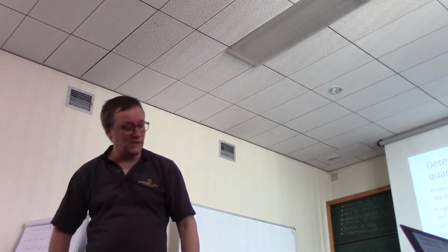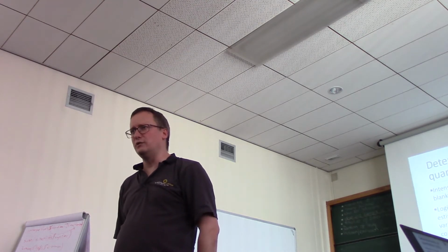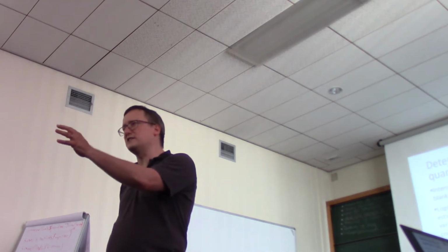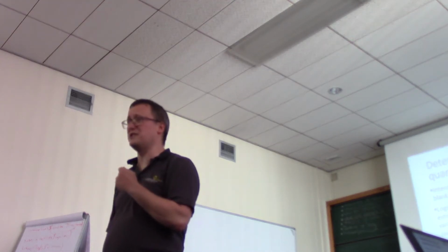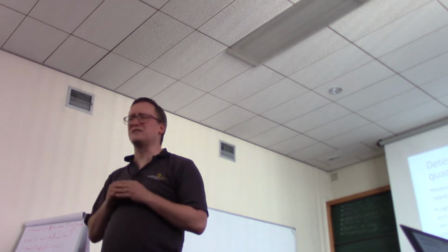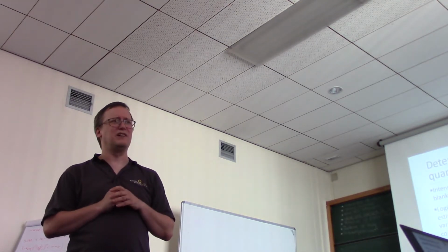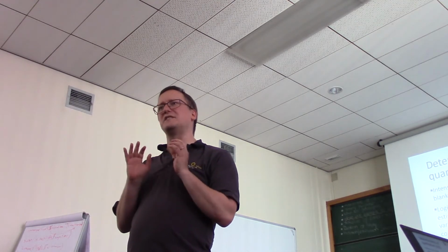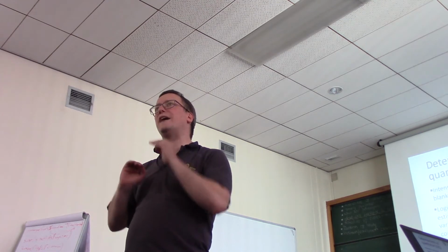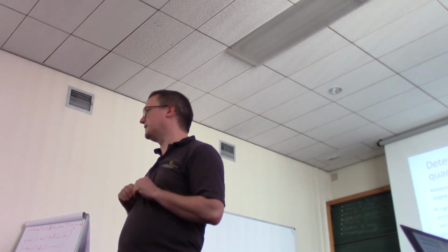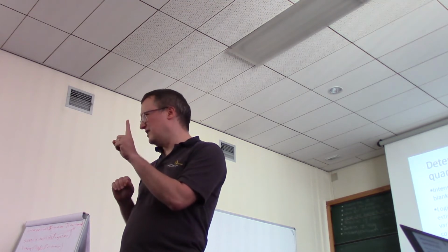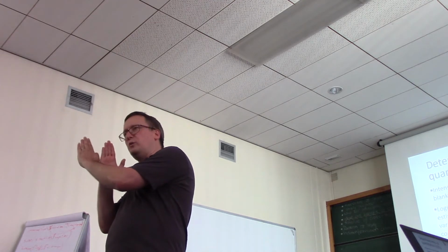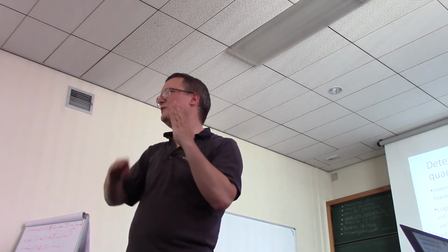Okay. So we've made passing mention now of LOD. We've talked about this logistic regression to fit levels of intensity versus known concentrations. Next, we need to talk about limits of quantitation. Limits of quantitation are, I think, kind of poorly understood, frankly. And part of this is the idea that people think, so long as you have enough sample, you're within the limits of quantitation. But it's not one limit of quantitation, it's two limits of quantitation. We have a value below which we can't detect, and a value above which we can't quantify, right?